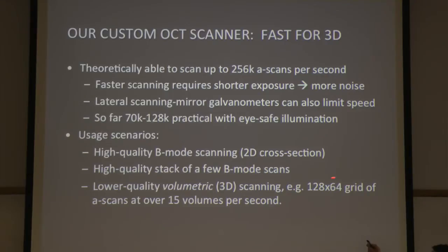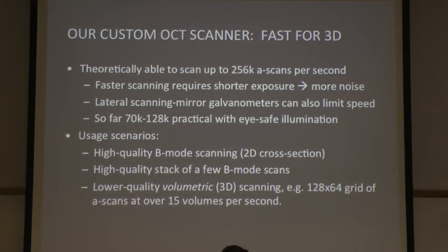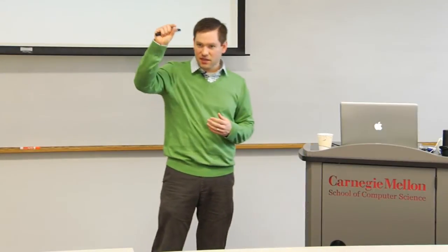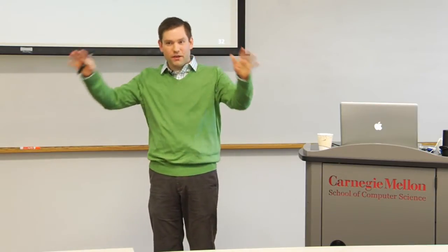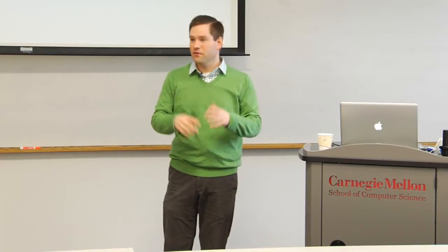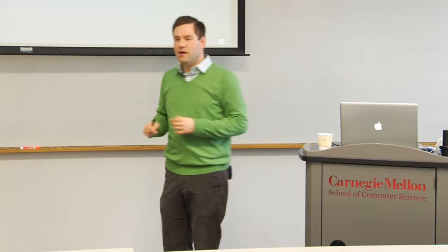You may be thinking that that's a really low resolution. And while it's certainly not as high as we might desire, it is sufficient for 15 volumes a second. And for most purposes, that resolution is perfectly acceptable, because most structures in the eye are layers. And in a layer, we care a lot about subtle differences in the depth dimension, where we have this 6 micron resolution. And because the layer is flat or gently curved, when you're at millimeter level scale, even the cornea is very gently curved. If we have a bit more coarseness in our samples, that's perfectly fine.